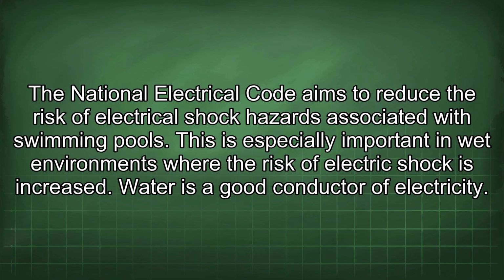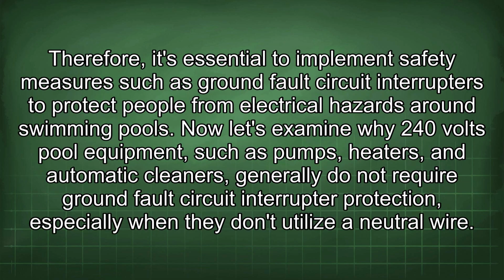The National Electrical Code aims to reduce the risk of electrical shock hazards associated with swimming pools. This is especially important in wet environments where the risk of electric shock is increased. Water is a good conductor of electricity. Therefore, it's essential to implement safety measures such as ground fault circuit interrupters to protect people from electrical hazards around swimming pools. Now let's examine why 240-volt pool equipment, such as pumps, heaters, and automatic cleaners, generally do not require ground fault circuit interrupter protection, especially when they don't utilize a neutral wire.